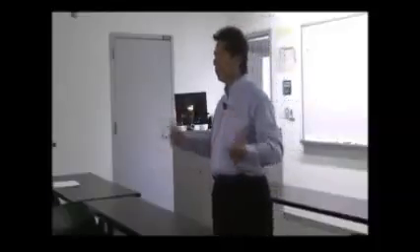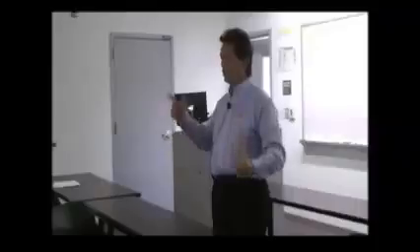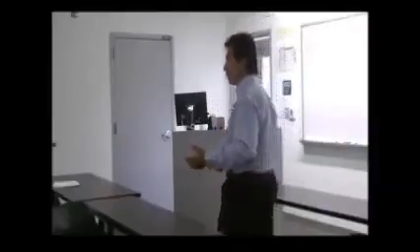So now I'm going to raise it up to a comfortable 70 or 71 degrees. So now I'm using two forms of energy. For that split second of time in that year, two systems are fighting against one another. I've got a lot of humidity. I can't bring it into the building, so I'm bringing out that air by dropping the air temperature. But yet, for the occupants at the end, I've got to heat that air back up. So we're very fortunate that we do live in Arizona for those particular ones.